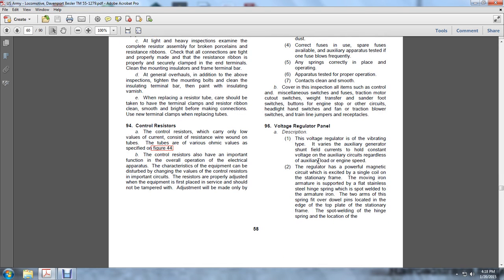96. Voltage regulator panel. The regulator panel is a vibrating type that varies the auxiliary generator shunt field currents to hold a constant voltage on the auxiliary circuits regardless of the auxiliary load or engine speed.